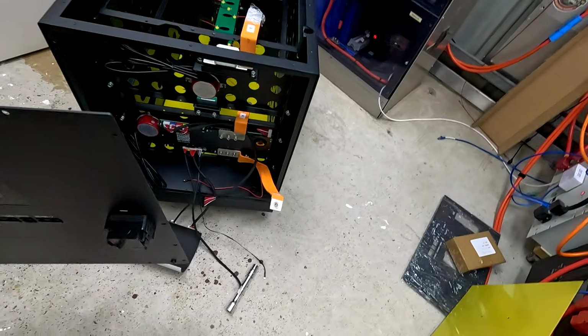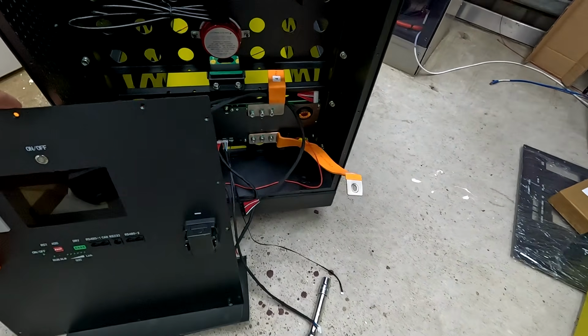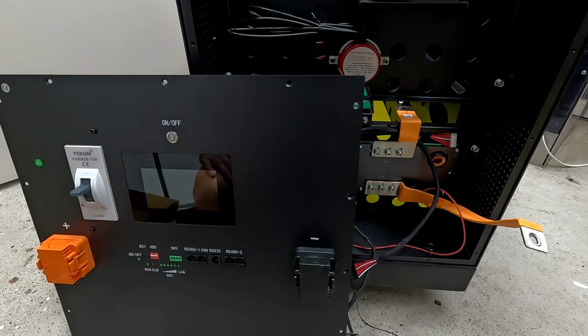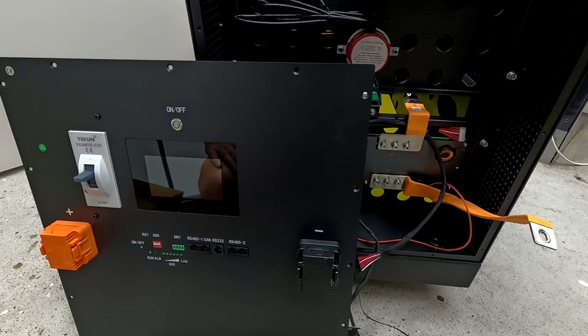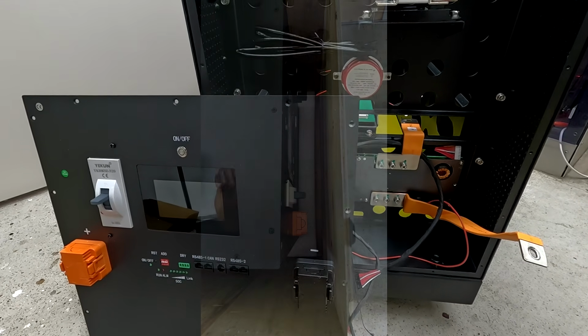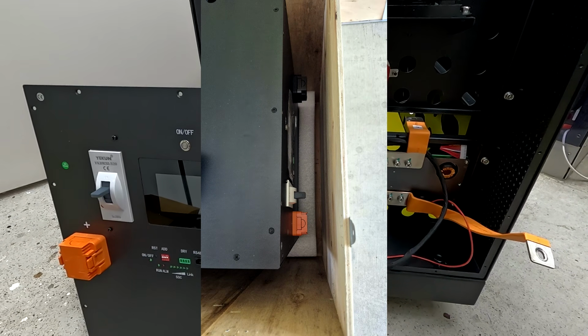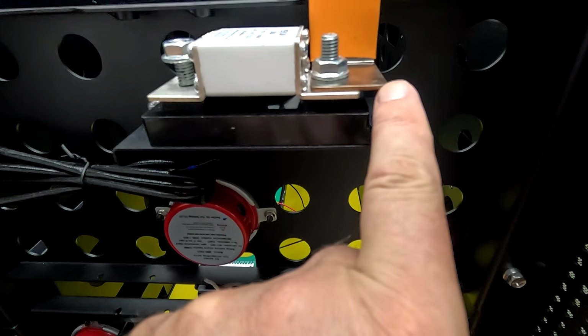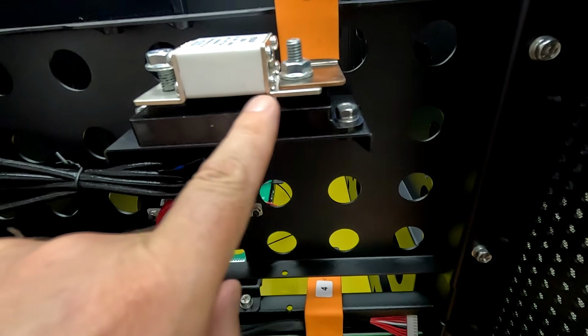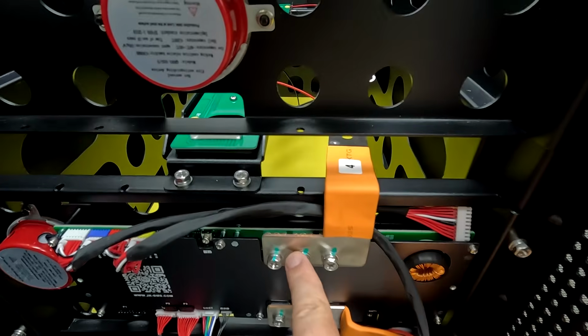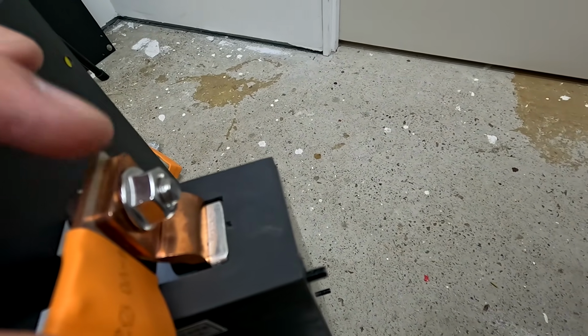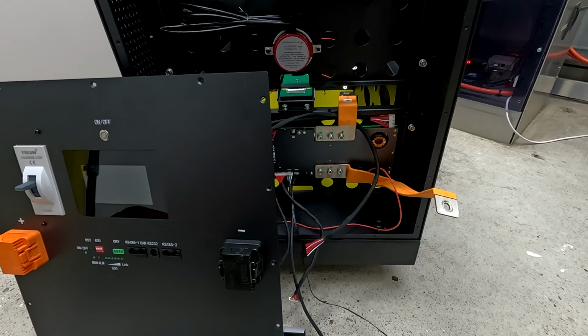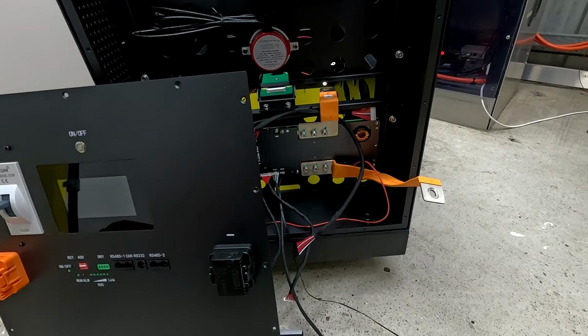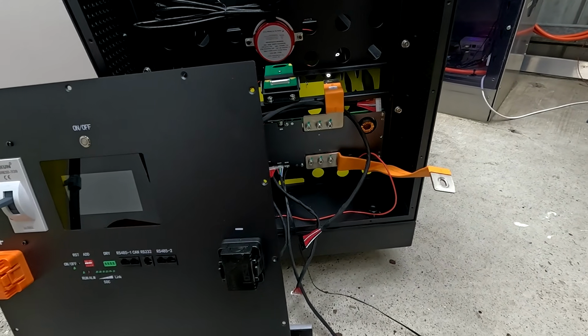Okay my friends, I think so far there are a few points I've shown you which may need attention or even improvement. Some minor issues with the packaging, I think it could do with a bit more, especially in the front. Then we have seen these different sizes of conductors and bus bars in several locations: here at the fuse, here at the BMS, the circuit breaker connection link, as well as at the bottom. And as you have just seen, the ampacity of these bus bars is only 80 amps.